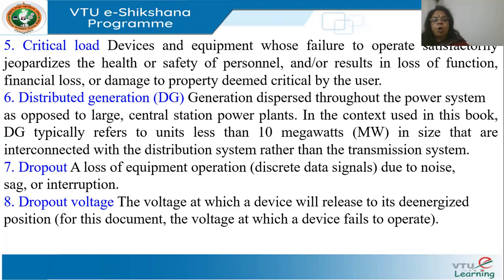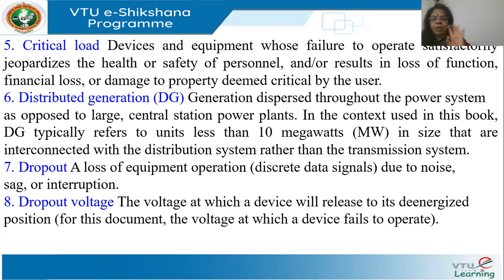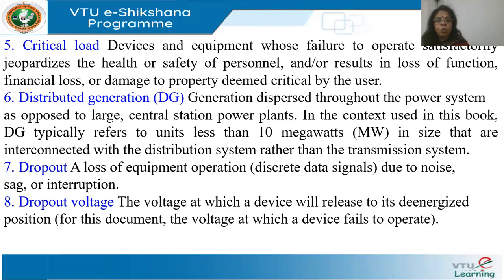Dropout is a loss of equipment operation due to noise, sag, or interruption — the equipment drops out of service because of a power quality disturbance. Dropout voltage is the voltage at which a device will be de-energized. For example, a relay has a threshold below which it will not work; a motor has a lowest voltage below which it will not operate. That is the dropout voltage — the voltage at which a device releases to its de-energized position.